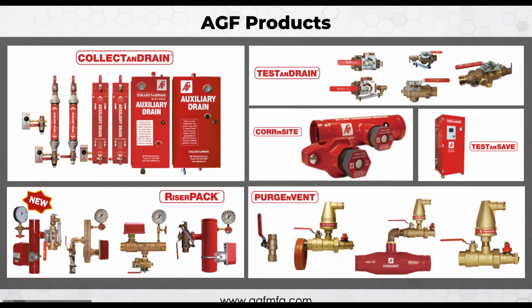So the flood eliminator would have prevented a significant amount of what happened in the Texas issue with frozen and broken drum drips causing damage, because it would have slammed closed, and you just have that little drip of water coming out of it till somebody can get in there, turn off the water, drain the systems down, repair the pipe. And the minute you repair the pipe and repressurize the system full of air or nitrogen, the best thing about the flood eliminator, it just resets itself. It doesn't require any form of interaction in resetting itself. Just once the system repressurizes, it's spring loaded, it immediately goes back to its normal open position.